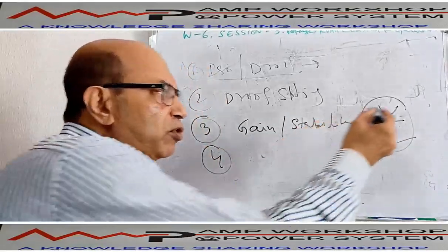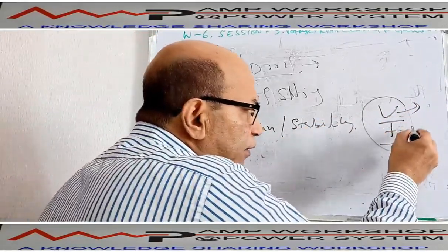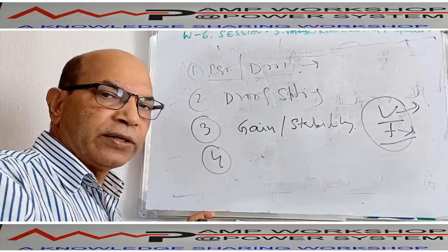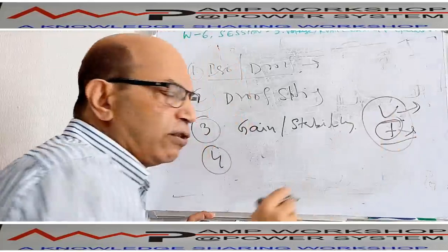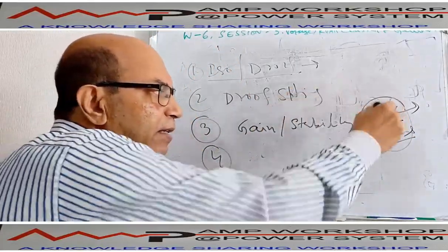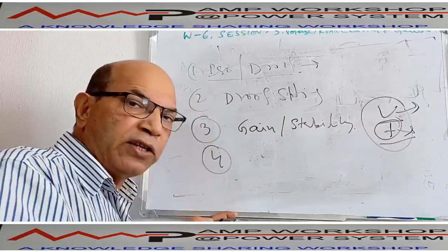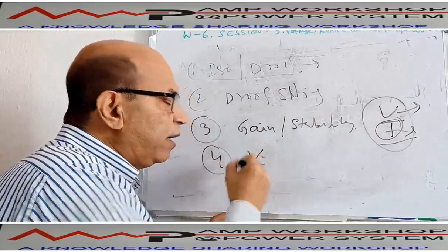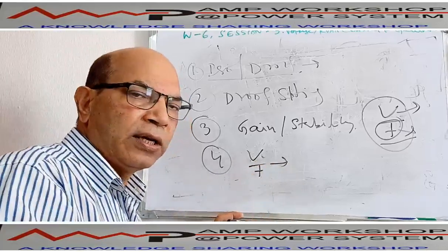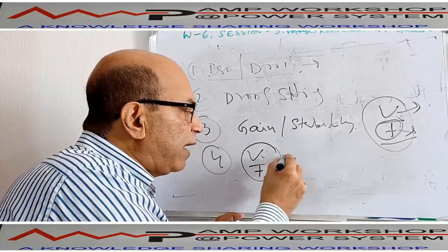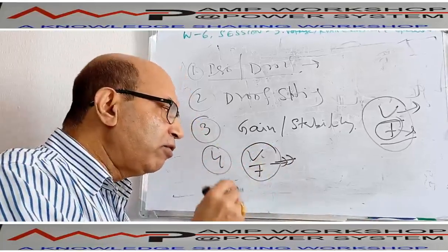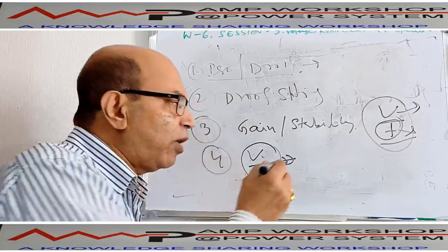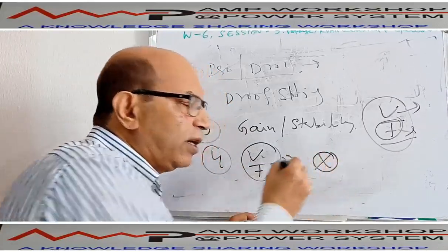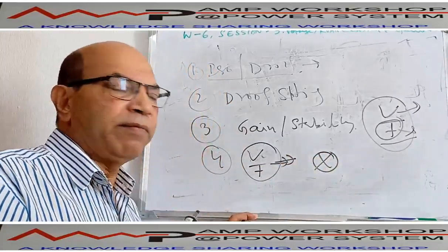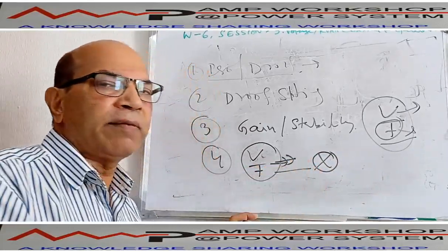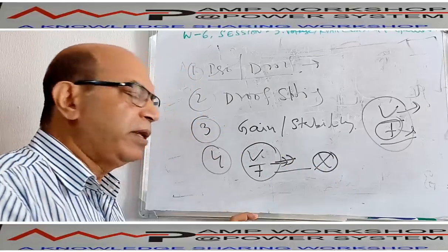So as the voltage is controlled by AVR and F is controlled by the governor, these have to be correlated. So this reference frequency is always coming to the AVR and AVR is monitoring the voltage. When the voltage comes below its setting point, then the V by F ratio will be very low. Immediately it will be dangerous for the machine. That's why it immediately gives an alarm. So this V by F ratio setting is there. If the V by F ratio comes below the setting point, then it gives an alarm or an indication that the machine is running on a low V by F ratio. So this is called the under voltage, under V by F ratio setting. That is also available in the machine.